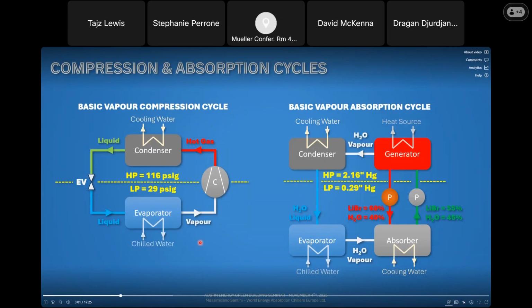As you know, in every chiller, the cooling effect is achieved by transferring the heat from the chill water to the liquid refrigerant. This heat transfer cools the chill water and heats the liquid refrigerant, creating a change of state from liquid to vapor. Then the refrigerant vapor has to be taken to the condenser to return to the liquid state and restart the cooling effect.